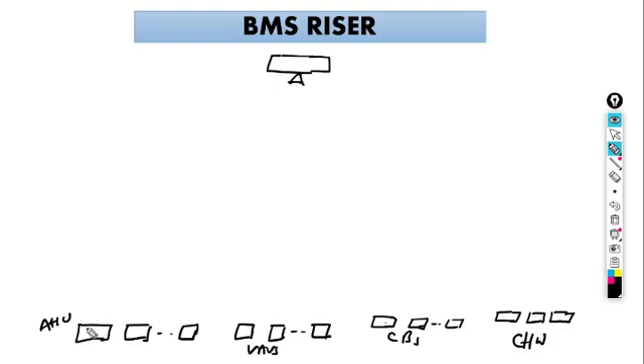In AHUs we have a chill water valve, so we need a chill water valve actuator to actuate it, and a controller for that valve. Suppose we want to measure the temperature of the air inside the AHU - there are temperature sensors, humidity sensors, CO2 sensors, duct static pressure sensors, and filter sensors (DPS). So there can be many kinds of sensors and actuators installed inside this equipment.